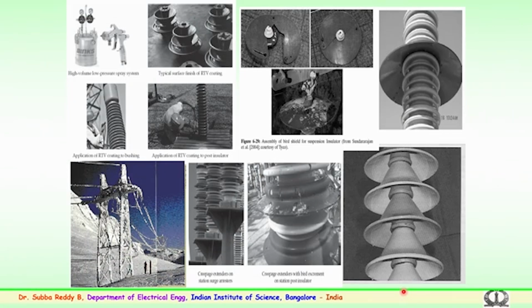Apart from this, you see various types of remedies employed to improve the performance of the insulator. This is one such small arrangement on the surface of the insulator to increase its creepage. Again, an insulating material known as a creepage extender is employed so that the insulator improves against bird droppings for a certain period of time. So, this also has been tried out. Again, this is for a substation post insulator, known as a creepage extender. It tries to see that flashover does not happen even when the surface becomes contaminated. This will help partially to prevent flashover.